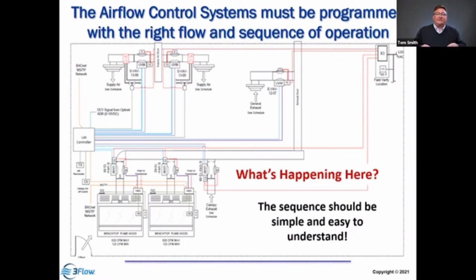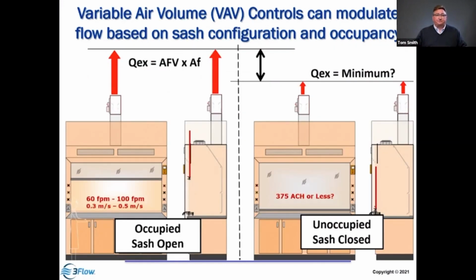We need to have an easier description that sets our expectations, and then have criteria. How low can we go? How fast must it respond? What's the maximum flow that's tolerable? What's the impact on room pressurization? These are parameters that we can get around the sequence of controls.